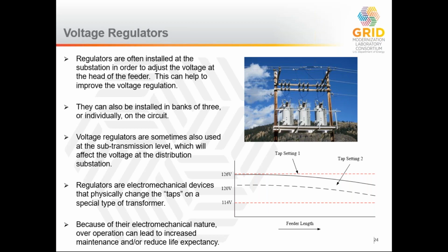So you can see in this case, you can move the voltage at the head of the feeder up and down, which will affect the voltage down the entire system. That level of flexibility allows you to accommodate changes as the load changes in the day. You can change your tap positions so that customers don't see the voltage drifting over the full range of the day. By actively tapping throughout the course of the day, you can keep the voltage in a much more narrow contained band. And for most utilities, you can even see this in your house. If you put a meter to the outlet, it'll only vary a little bit.